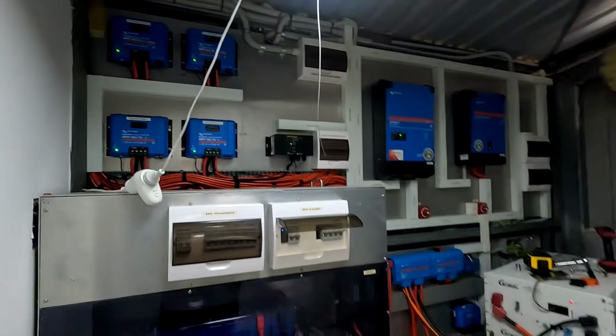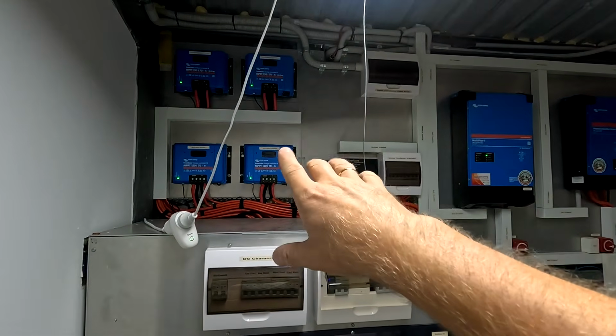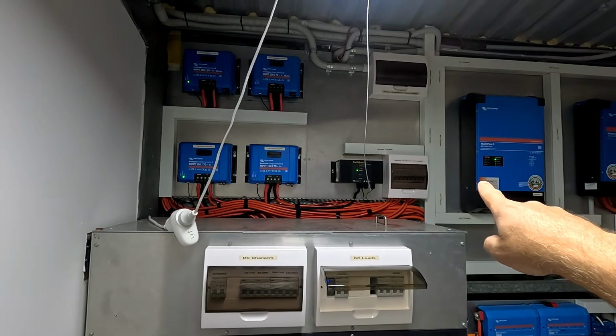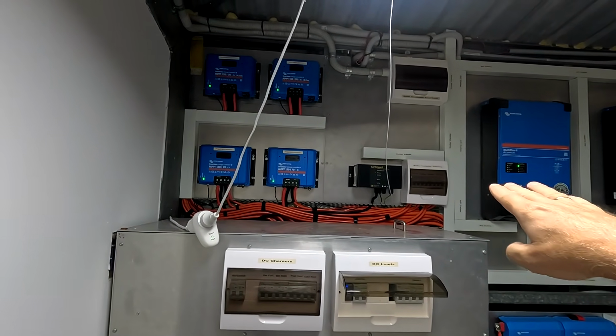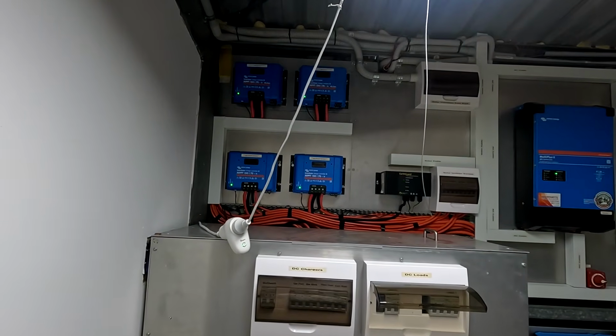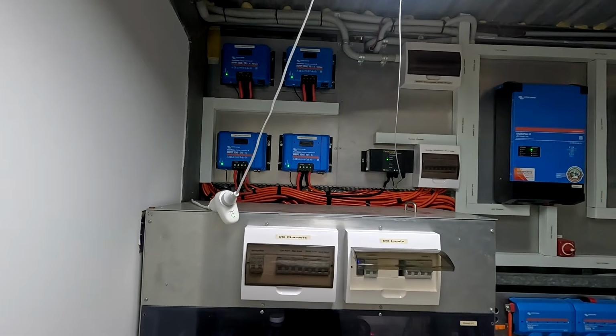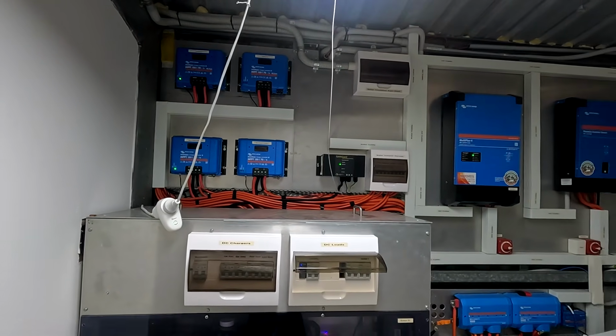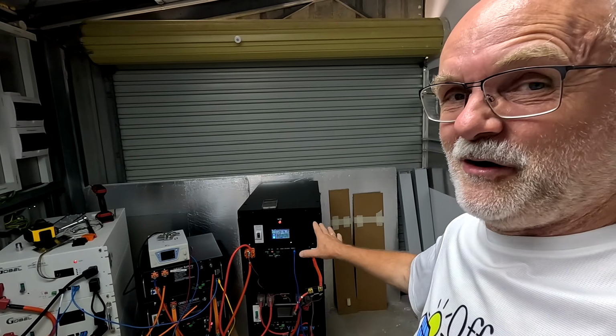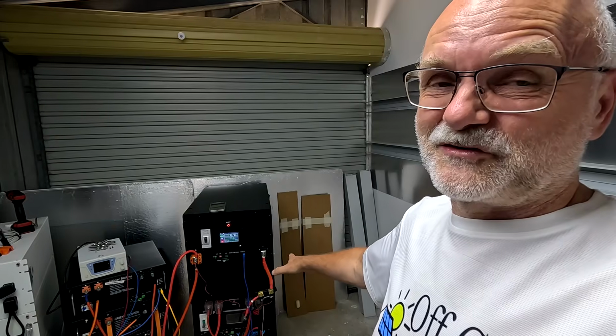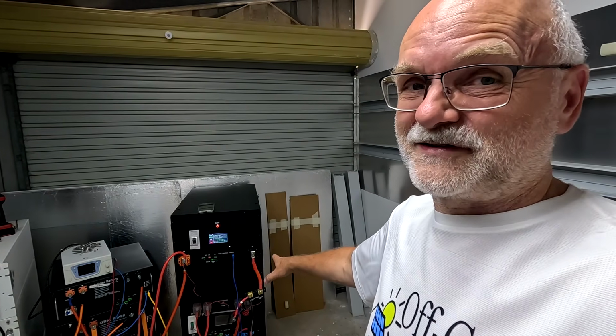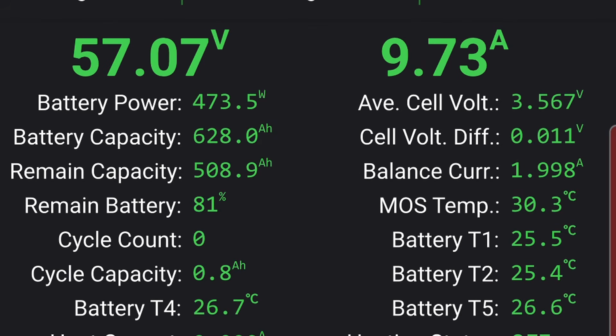good to go. Of course, we also have to turn off all the solar chargers. Yeah, I will flick the breakers up there. This disconnects all the solar incoming into these MPPTs. I've already turned off the tilt system, so there's no AC power coming into the multi-plus anymore, because we only want to discharge this battery now. Yeah, there should be no charge coming in, because this will of course offset our result then. It would be wrong. We are still charging and discharging depending where the current is coming from, because this is the only battery at the moment in the whole system.